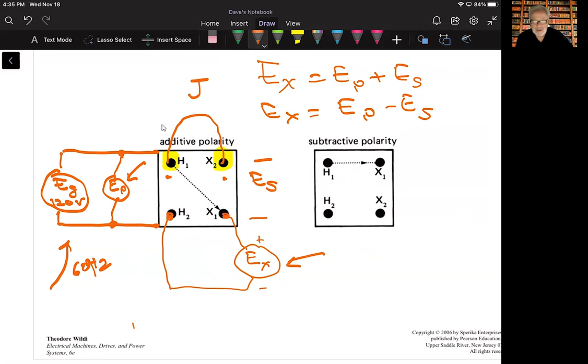In example 10.3, it says during a polarity test on a 500 kilovolt amp, 69,000 volt, 600 volt transformer. Of course, this would be the primary and this would be the secondary, so it's a step down transformer with 69,000 in and 600 out.